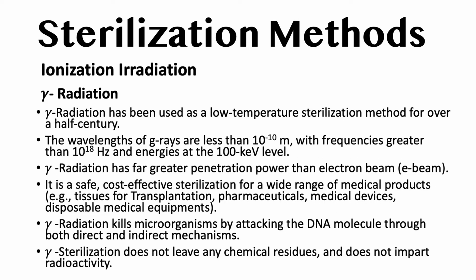Gamma radiation has been used as low temperature sterilization method for over a half century. The wavelengths of gamma ray are less than 10 exponent minus 10 meter, with frequencies greater than 10 exponent 18 Hz and energies at the 100 kiloelectronvolt level. Gamma radiation has far greater penetrative power than electron beam. It is safe, cost-effective sterilization for a wide range of medical products like tissue for transplantation, pharmaceuticals, medical devices, disposable medical equipments. Gamma radiation kills microorganisms by attacking the DNA molecules through both direct and indirect mechanisms. Gamma radiation does not leave any chemical residues and does not impart radioactivity.